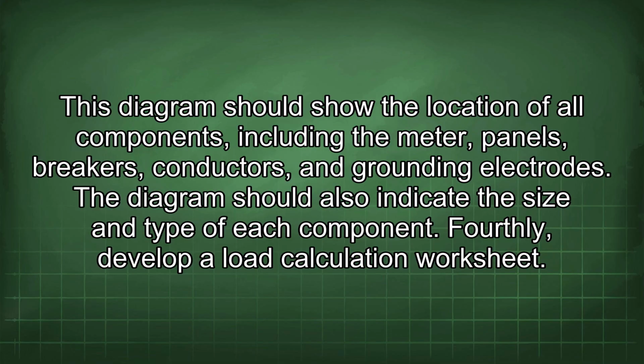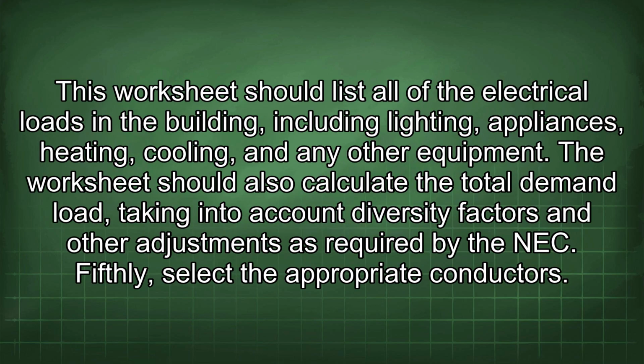Fourthly, develop a load calculation worksheet. This worksheet should list all of the electrical loads in the building, including lighting, appliances, heating, cooling, and any other equipment. The worksheet should also calculate the total demand load, taking into account diversity factors and other adjustments as required by the NEC.